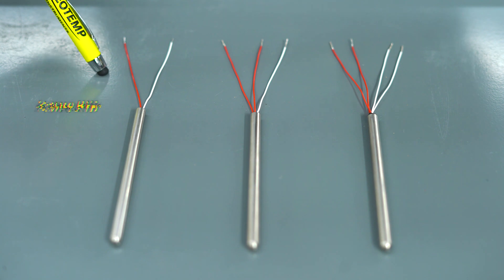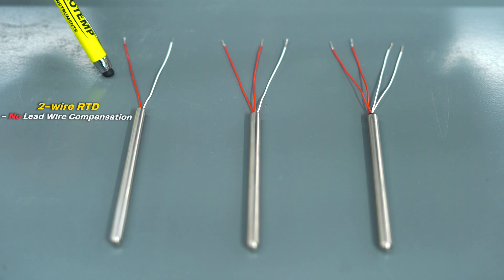Technically you only need two wires to build an RTD, but if the temperature reading is a result of measured resistance across the element, then what about the resistance of the lead wire? In a two wire RTD, this extra lead wire resistance is not accounted for, creating inaccuracy.